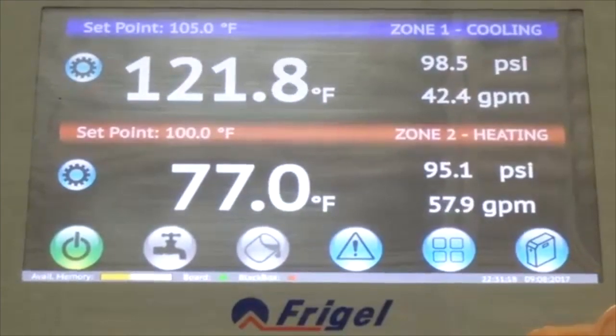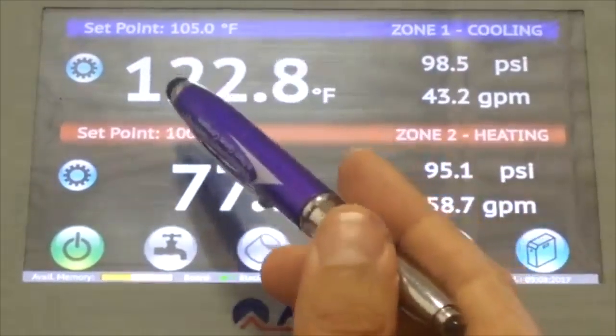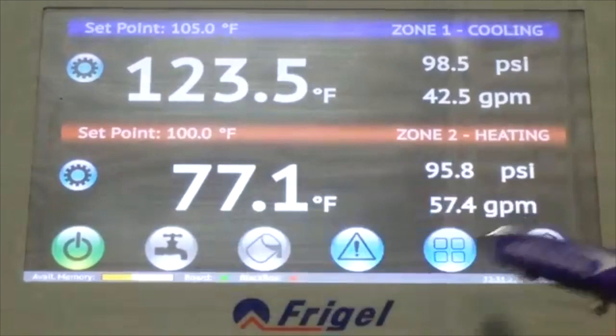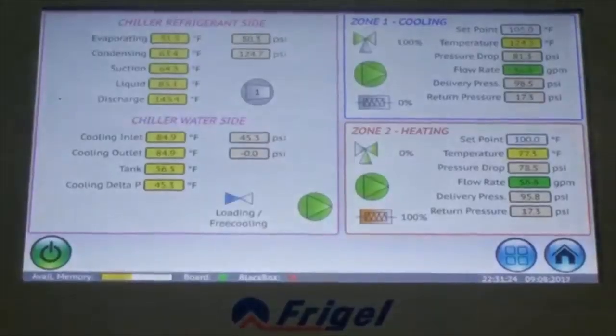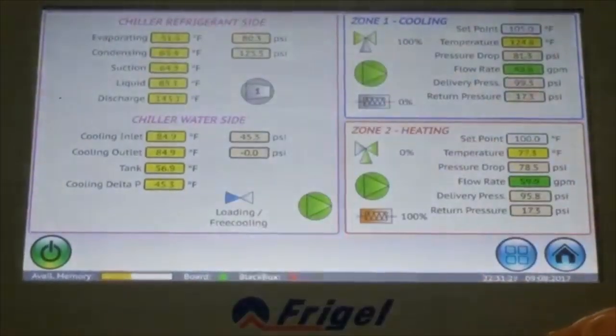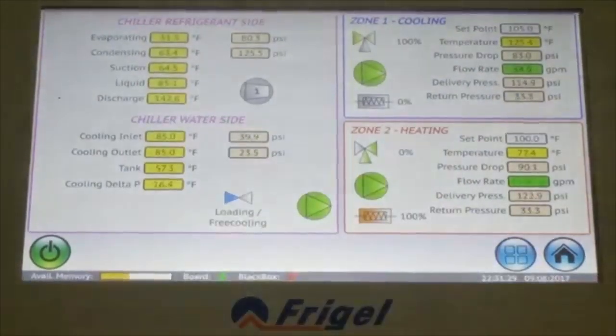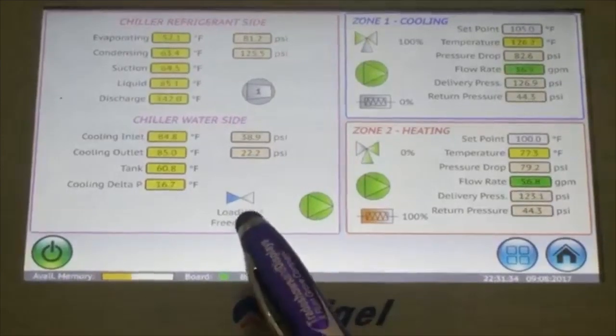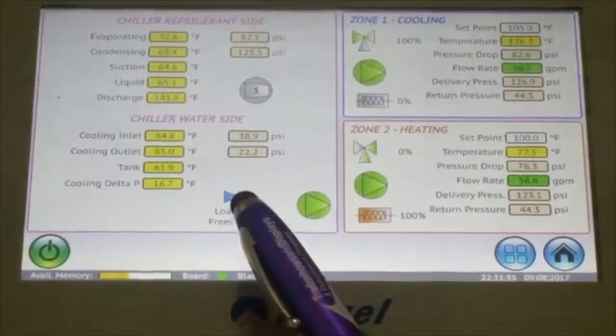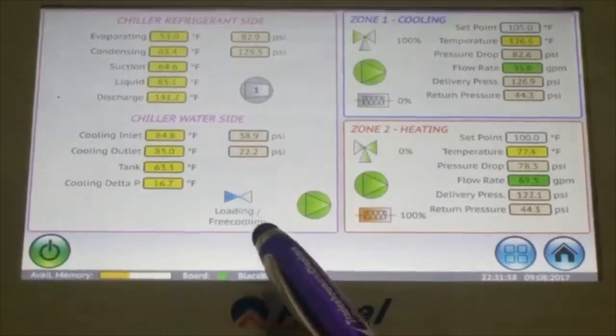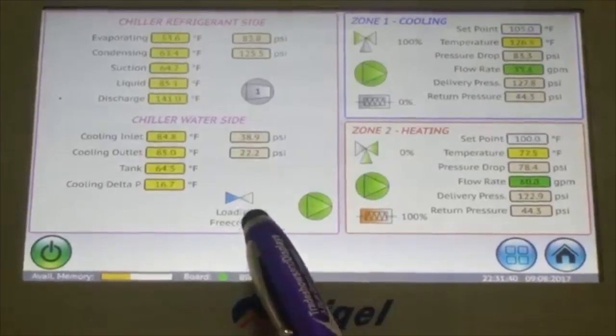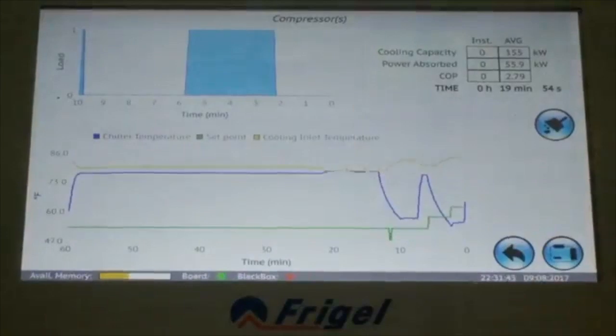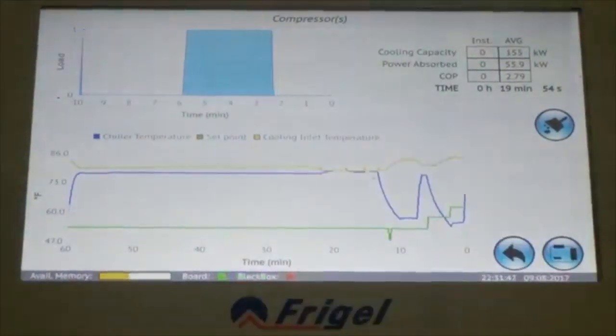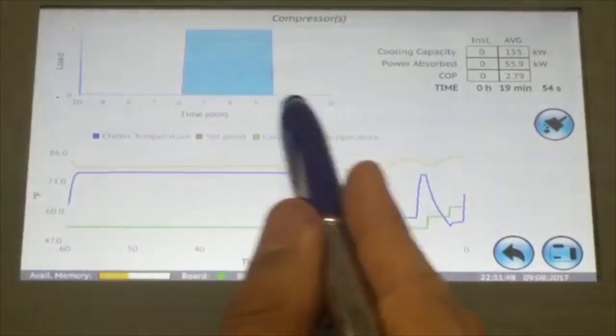In this instance, one zone is in cooling mode, the other in heating mode. The set points are 105 and 100 degrees Fahrenheit. Switching to the unit parameters screen, the inlet temperature from the EcoDry system is 85. Notice that the compressor icon is gray or off mode. Also, the free cooling valve is blue, indicating the unit is now in free cooling mode. In the refrigeration screen, you can see that the compressor is now off.